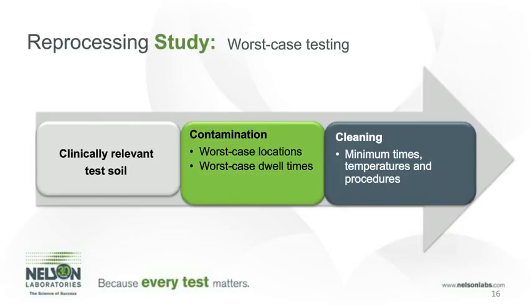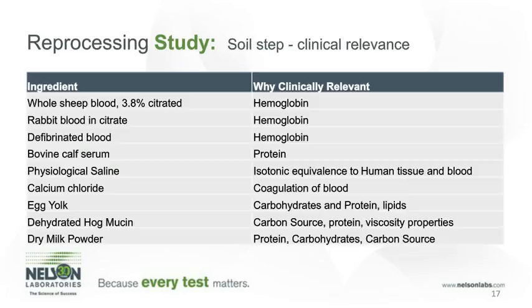performed correctly. I presented this information to the FDA in 2011 and have never been questioned on our test soil since. On the left are all the ingredients that may be utilized in test soils, and the right column shows why the ingredients are clinically relevant. So we take these types of ingredients and put together a clinically relevant soil that is exact for the simulated use of the device that will test the exact surgical procedure that is utilized for the device. FDA now recommends the specific test soils we utilize for validations to other companies that they have.